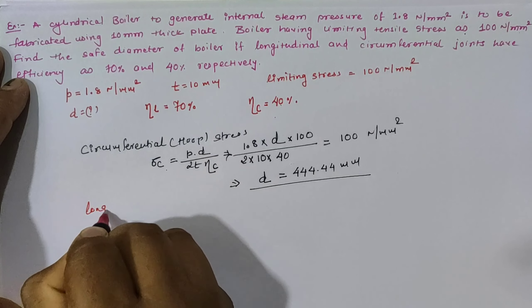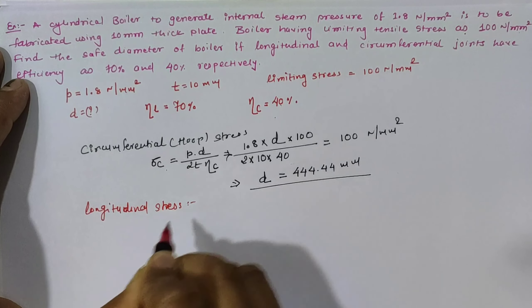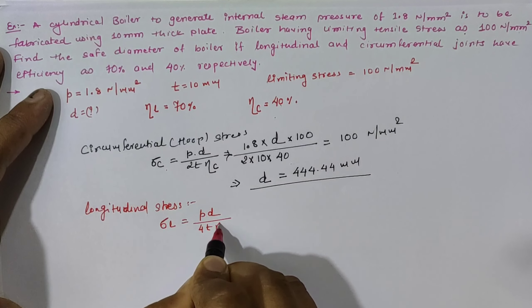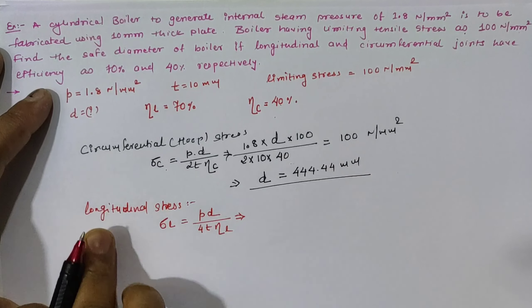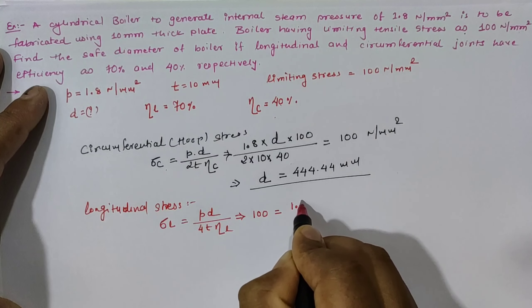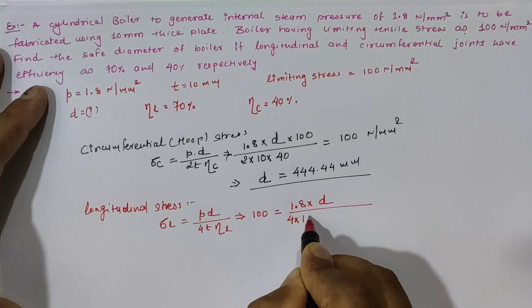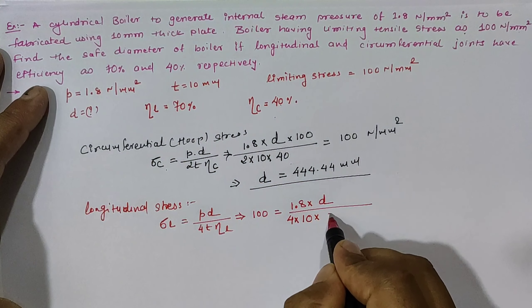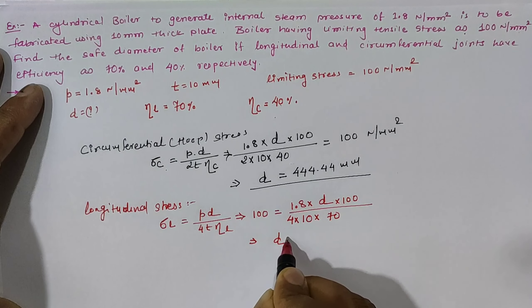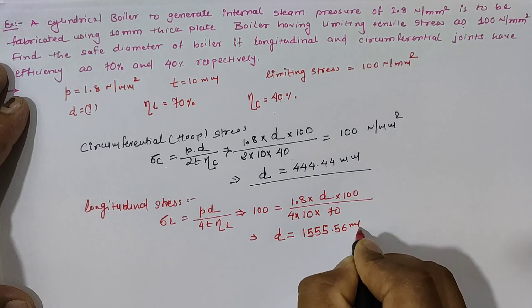Now calculating longitudinal stress: sigma_l = pd / (4t × efficiency). Setting the maximum longitudinal stress to 100 Newton per mm square, substituting pressure = 1.8, t = 10 mm, and longitudinal efficiency = 70/100, solving gives diameter = 1555.56 mm.